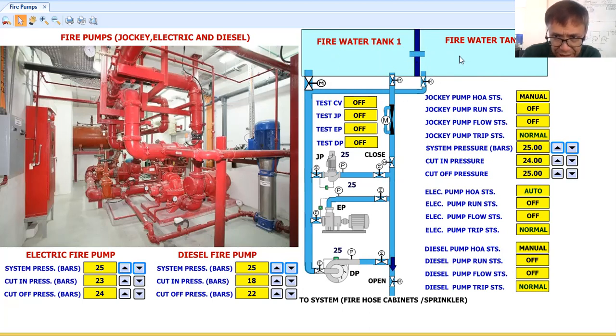As you can see here, from both tanks there will be a suction line. My main suction line here should be a little bit bigger to make sure that there will be a net positive suction head. Because if you do not properly size this main line or main header, then if the electric fire pump runs, the pressure keeps on dropping, and your diesel pump will kick in. Maybe you will not be able to get the proper flow or suction pressure in your pumps. So as a mechanical engineer, it is their responsibility to make sure that all the pipes are properly sized and designed.